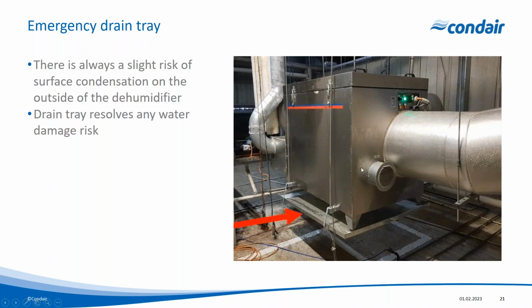Now, inside this unit, we've got air that's coming from the cold store, so it's minus 27, minus 28 degrees C. So we have 100 mil thick insulation internally to stop any heat transfer. But even though you've got 100 mil insulation, if you've got a warm, humid environment on the outside of that dehumidifier, you have the risk of condensation forming on the outside of the unit. So it's good practice to mount it on a drip tray. And you can see that it's here below the unit. We've got the unit mounted on a drip tray that's just attached to a trap drain. So that just prevents any damage happening underneath the unit.